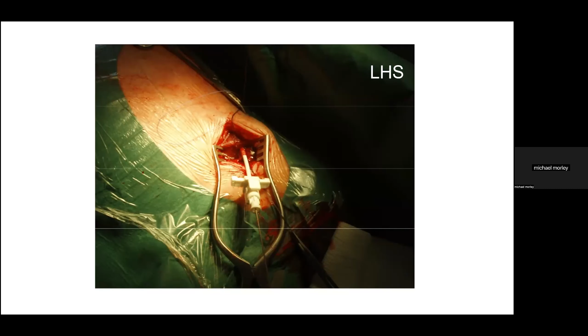The leads have a hollow core, which allows us to pass a stiff wire or stylet. Without the stylet in position, the lead is a bit like a piece of string, and trying to push a piece of string in the direction you want it to go is near impossible. With the stylet and with shaping the stylets, we're able to make the lead stiff, and that allows us then to push the lead forwards and position it to where we want it to be.